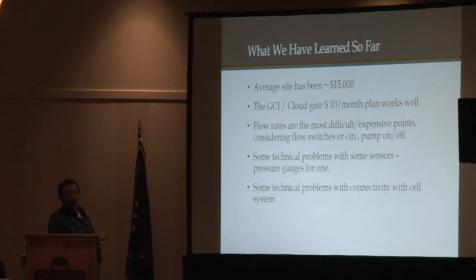Flow rates are important to know the water's moving out through the system in town, and that's really desirable, but it's the hardest point to set up. They're the most expensive, so we're looking at alternatives - just watching whether the circulation pumps are on or off, or potentially a flow switch, watching temperature of water going out and coming back. We may not be doing the flow rates much more because it takes so much tinkering to get them to work right.